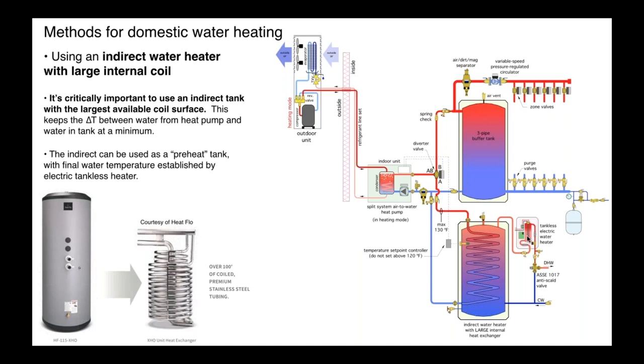The requirement here, let's say that we're looking for 140 degree water and we're concerned about Legionella. We want to get that water temperature up, or we need higher water temperature for sterilization, perhaps in a healthcare facility, something like that. Well, we aren't going to get 140 degree water coming out of this tank, regardless of how big this coil is. So we need some kind of a boost there.